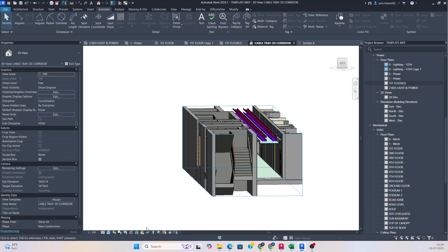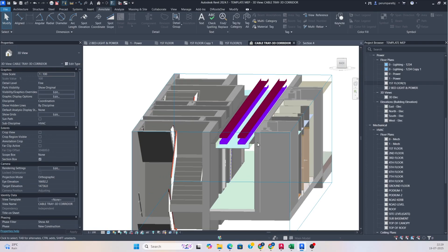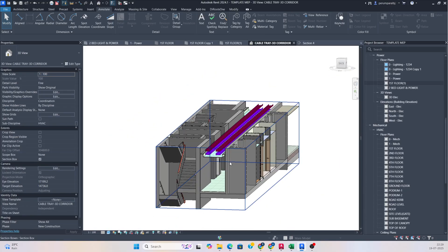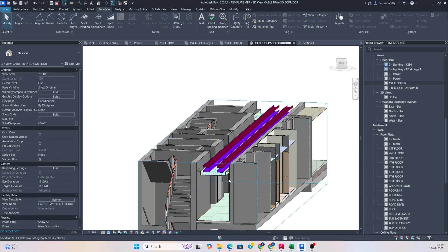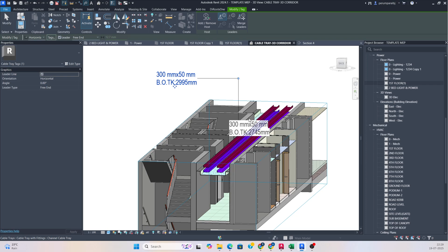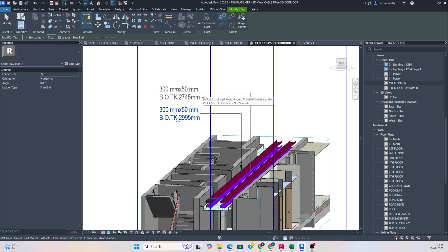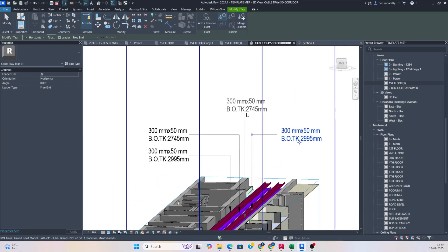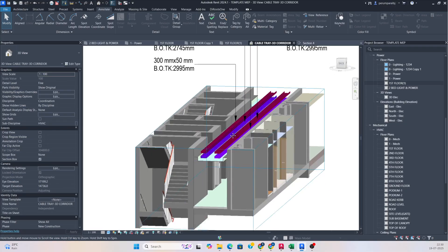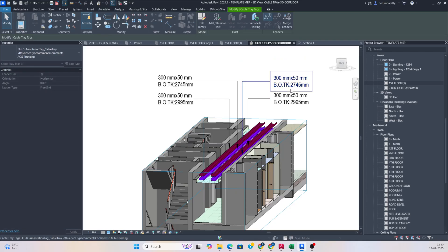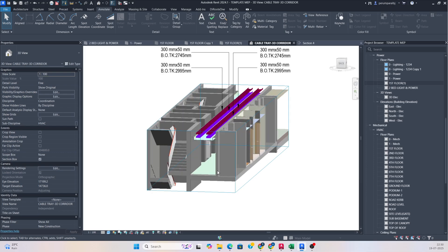Now you cannot rotate this view. If you want to rotate it, you need to go here, unlock the view, rotate it, then save and lock the orientation again — it will not move. Then use the shortcut TG for tag, and you can easily give the tag for the cable in the 3D view itself. From here also you can give the tagging for this cable tray and the below cable tray — just select and tag like that. You can save and properly arrange the tags.